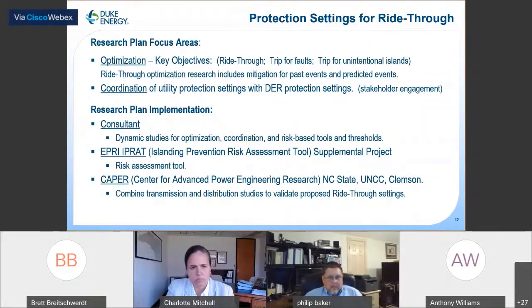This event is included in that research proposal. And then there's coordination of settings with the DER settings. At sites typically bigger than a megawatt, Duke has a protection device installed at the site, so the settings in the Duke devices have to coordinate with the settings in the DER facility, whether that's onboard settings or plant level settings. That's going to require a good bit of stakeholder engagement as we go through this coordination exercise.